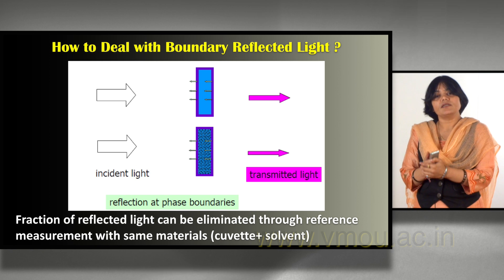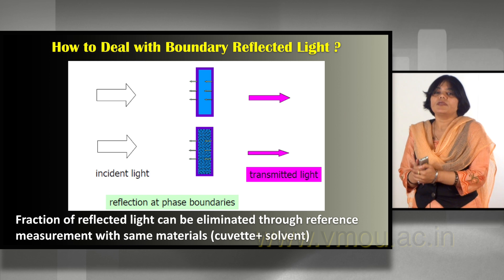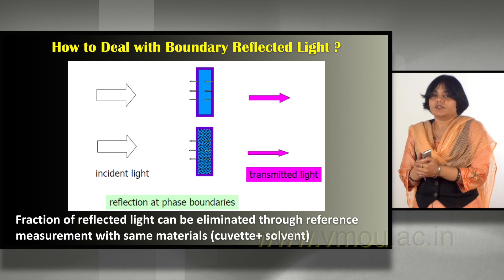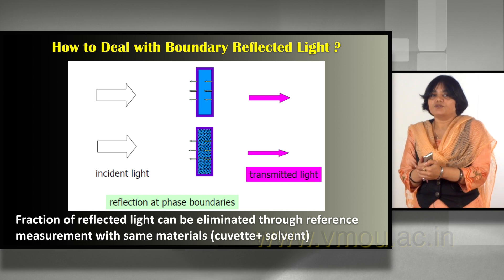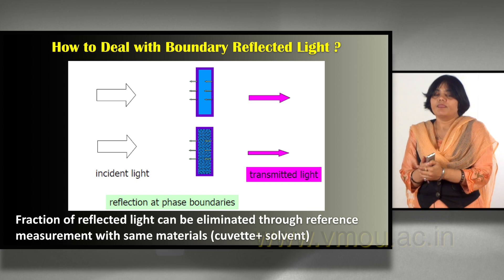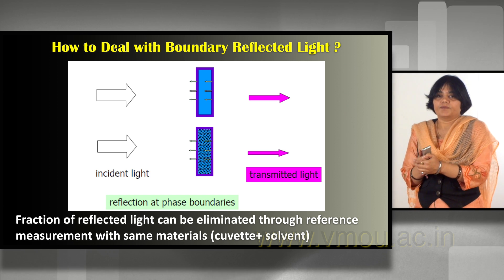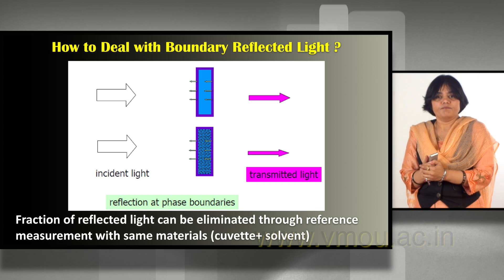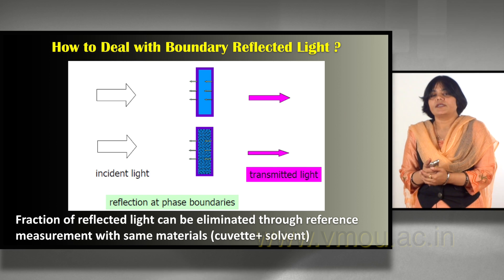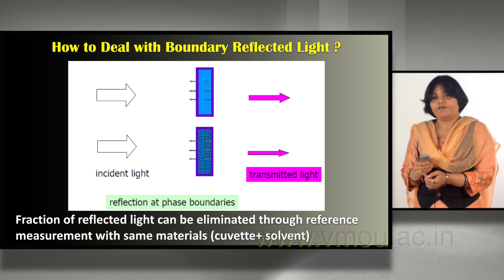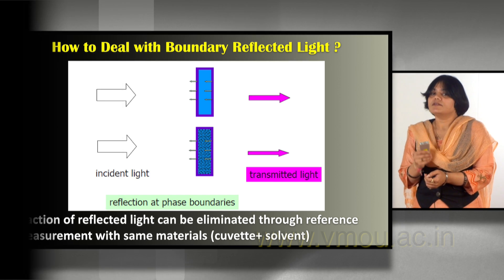To calculate the accurate portion of transmitted light, we first place a simple cuvette with solvent, then under the same conditions place a cuvette with the required solution in the same solvent. We then subtract the absorbance and reflectance contribution of the cuvette and medium, and we can directly obtain the transmitted light portion from the required sample.